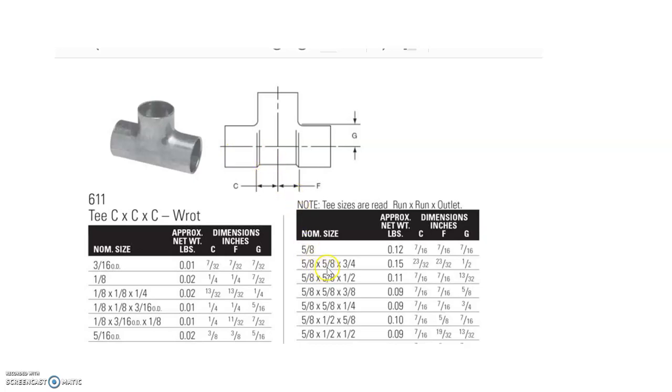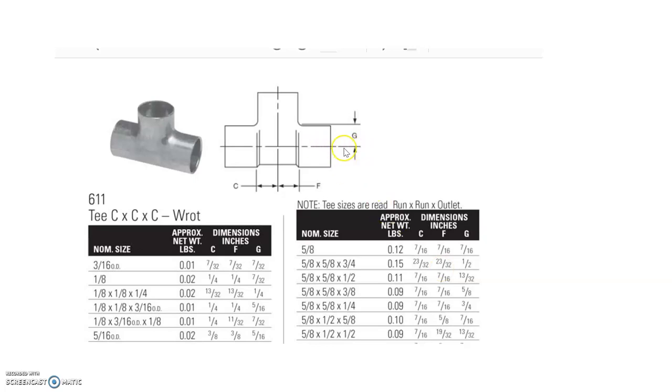The second one, the other 5/8" port which is on the opposite side, is notified as the F and it has a fitting allowance of 23/32". So again, on the opposite side, it's referring to the F dimension for it, and that is 23/32", the FA for that side.